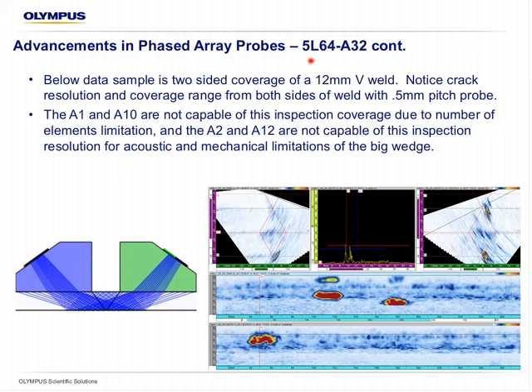The 5L64A32 would replace the A2 and the A12, and in many cases also the A1 and the A10. Where we don't need a very small wedge footprint for smaller welds, and where we don't need a 1 millimeter pitch element for very long sound paths and heavy wall piping in vessels, the 5L64A32 is our premium inspection with the new Weld Series wedge in the most common range of weld thickness between about 12 and 25 millimeters, and is inherently uniquely qualified for B31 piping inspection.